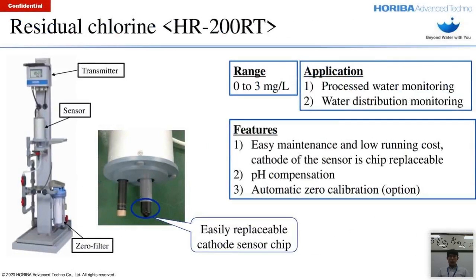Next slide, please. Okay, so next, for residual chlorine, we have HR200RT. Some of the features include easy maintenance and low running costs because the cathode sensor of the entire sensor is replaceable, as you can see in the picture on the left, the black arrow. And next, pH compensation. The concentration of residual chlorine is affected by the pH level, so it is very important to keep the pH level of the water always around pH 7. By using the pH compensation function, it helps to ensure that the measurement reading is stable even when there is a slight fluctuation in the pH level.